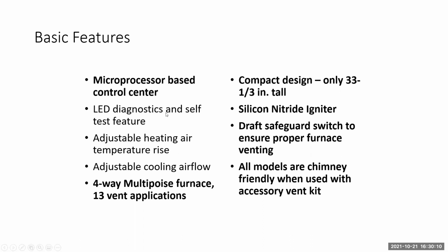Kind of talking boards here for a minute. The big thing is they've made the LED bigger and brighter for all of us blind guys to see. It's not real hard to see these anymore. It's none of that turning your head at 35 degrees, 45 degrees down just to see that LED. It's going to be right there in front of your face, pretty visible without really hunting for it. You've got adjustable cooling and heating airflows, and we are still 4-way Multipoise furnace, 13 vent applications. They're smaller furnaces. They all use the silicon nitride igniter unless somebody's changed it out afterwards.